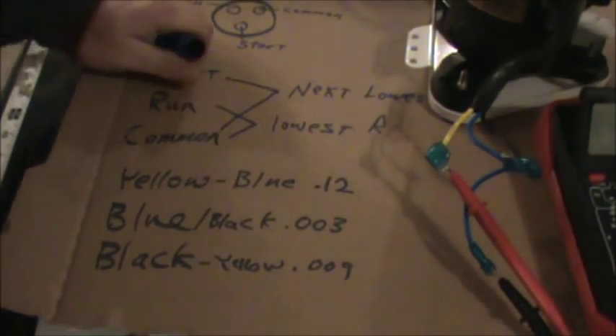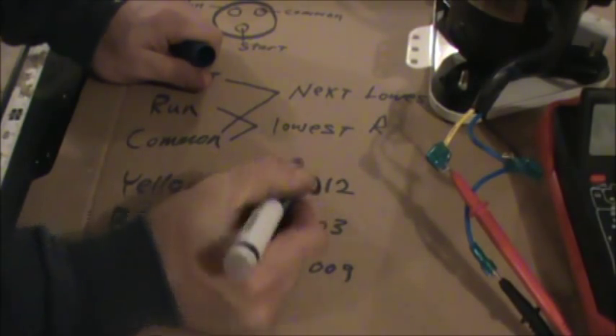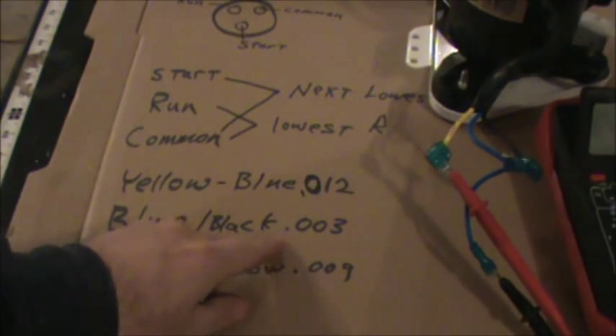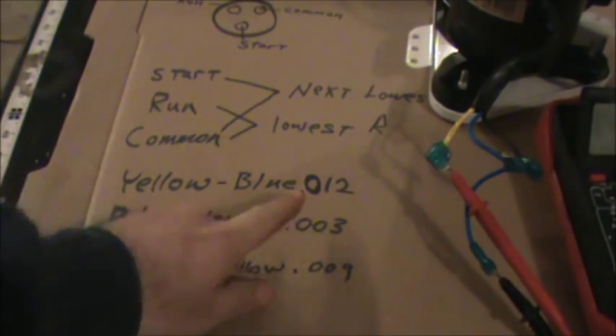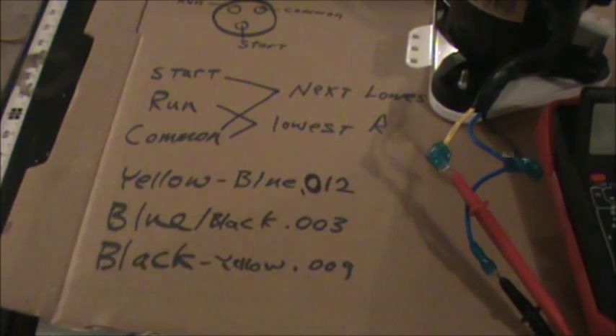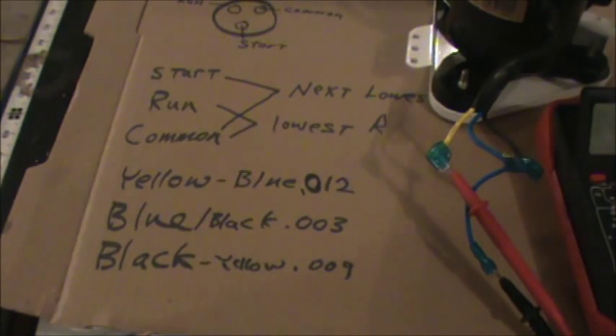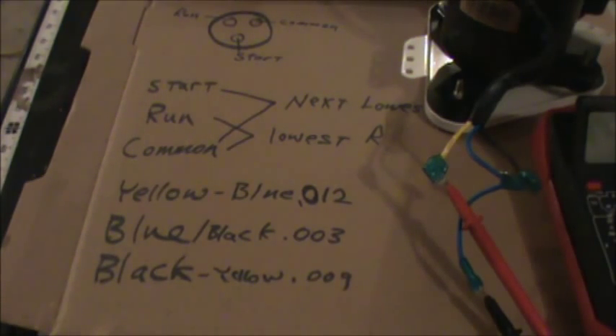So looking at my numbers, I realize I made a little mistake. This was 0.012. Just by looking at your numbers, if you add these two together, 0.003 and 0.009, it equals 0.012. That's a sign that your compressor is in good shape, and the wiring inside of it is in check. If those numbers are way off, they don't add up, then there could be a short or something like that. Alright, so here's how you determine this. Now you have all your measurements taken as far as resistance.